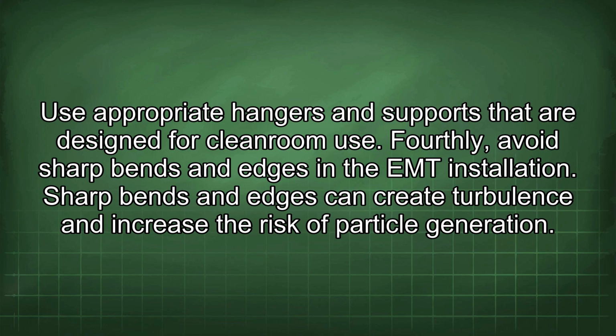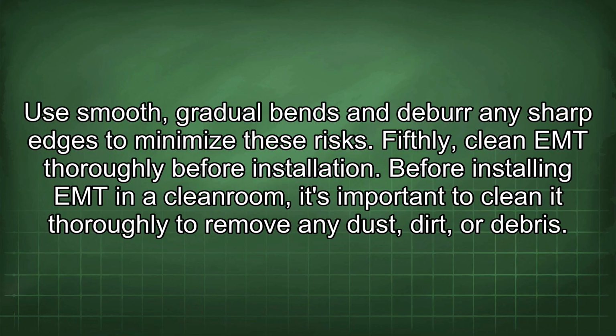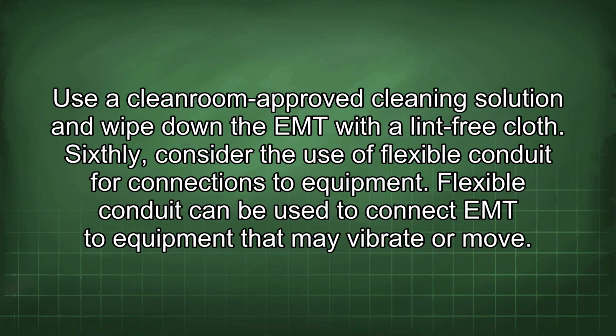Fourthly, avoid sharp bends and edges in the EMT installation. Sharp bends and edges can create turbulence and increase the risk of particle generation. Use smooth, gradual bends and deburr any sharp edges to minimize these risks. Fifthly, clean EMT thoroughly before installation. Before installing EMT in a cleanroom, it's important to clean it thoroughly to remove any dust, dirt, or debris. Use a cleanroom-approved cleaning solution and wipe down the EMT with a lint-free cloth.